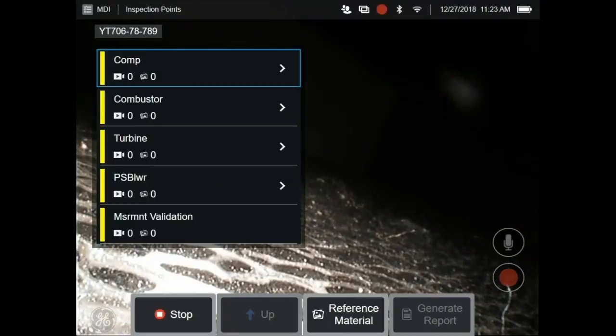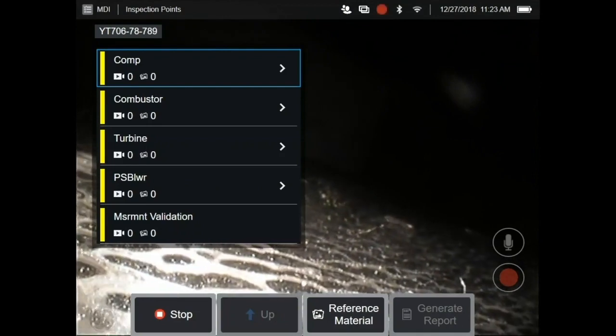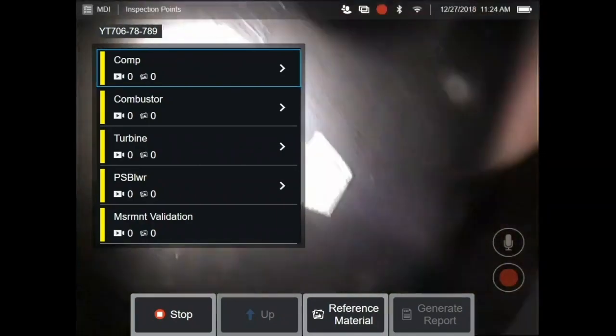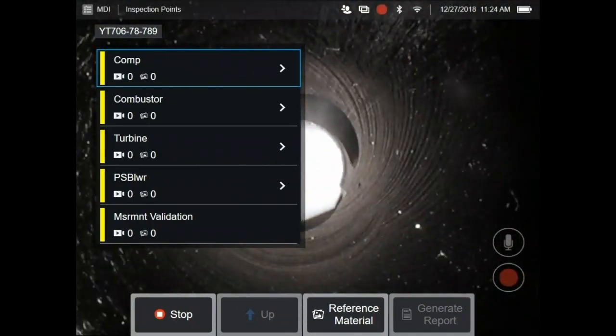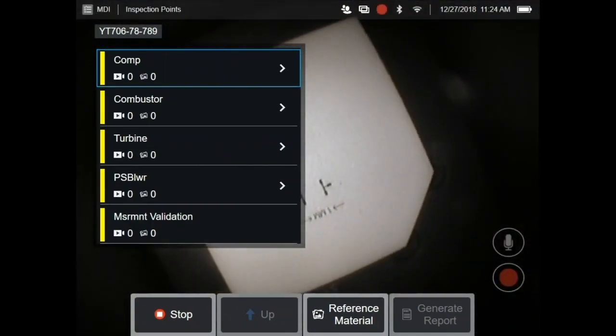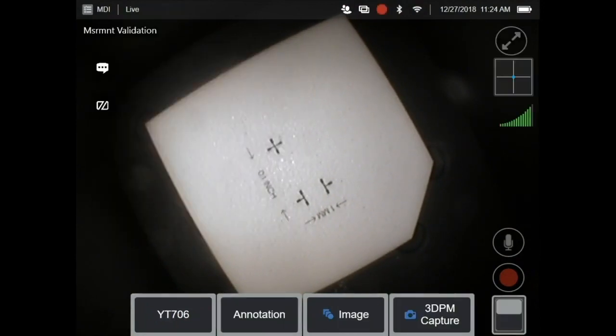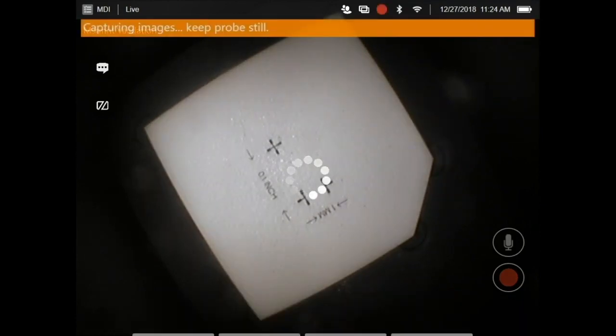And now I'm going to actually measure something in an asset, and the first thing that I will want to do is actually look at a target. This is an NIST traceable target, and down on the bottom you see I'm doing a measurement validation. That NIST traceable target I'm able to measure upon and determine if this scope is in calibration.